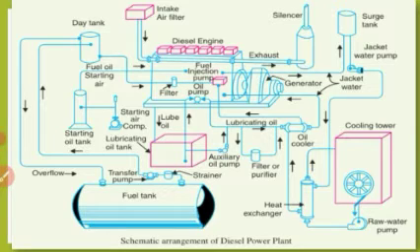What they will do first is admit high pressure air to a few of the cylinders, making them act as reciprocating air motors to turn over the engine shaft.